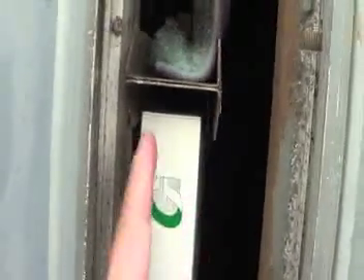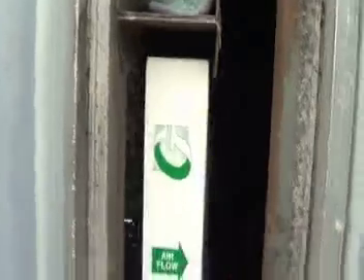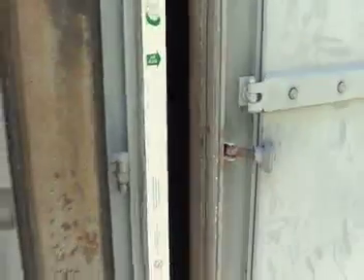Now look, here you have a huge gap. Look at all this play, all this bypass. All this is getting past the filters and going downstream and contaminating your system.